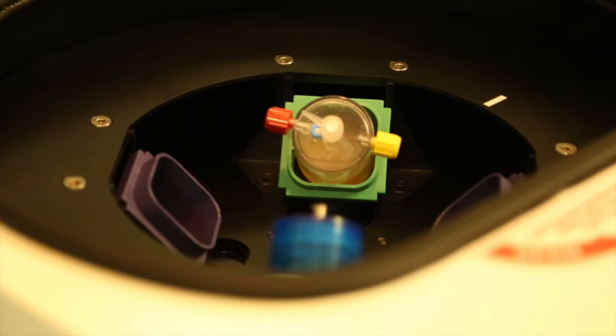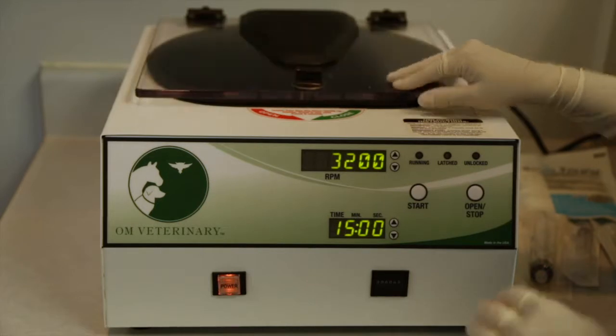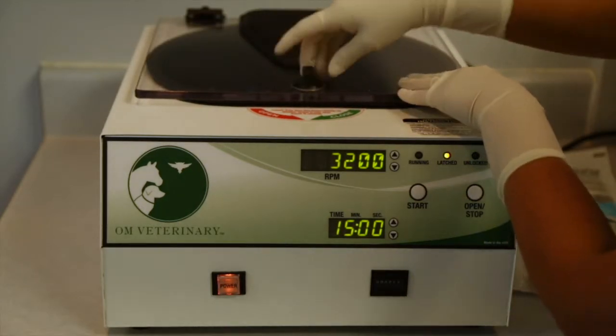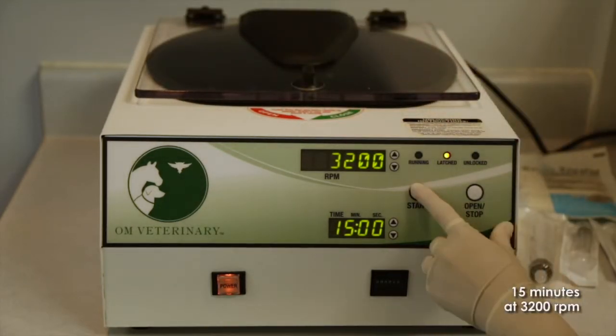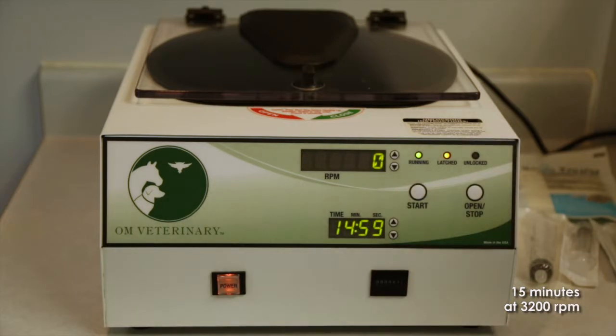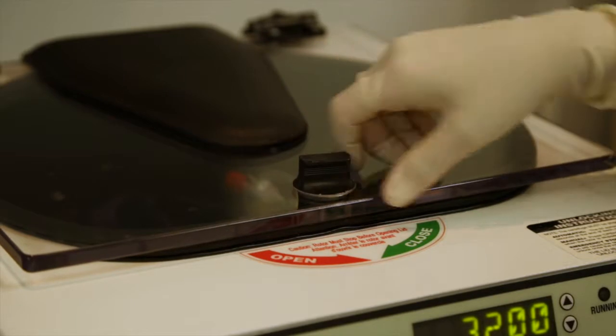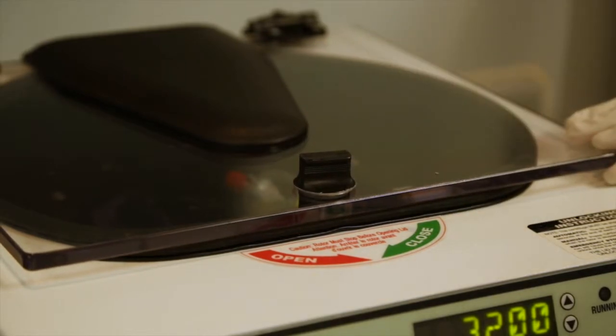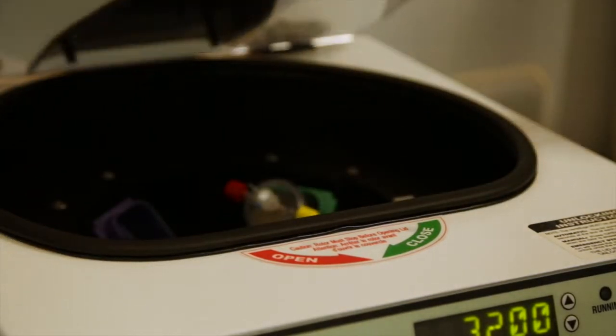Try to consistently use the same amount of ACDA and draw the same amount of blood. The total volume in both tubes should be the same to ensure the machine is balanced. Close the centrifuge lid and secure by turning the latch clockwise. Set the RPM to 3200 and time to 15 minutes and push the start button. At completion of the 15-minute spin, press the open button. Open the top latch and remove the device.